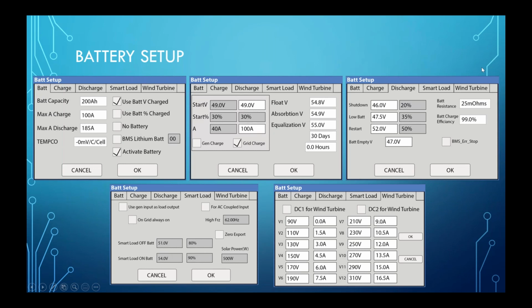And then BMS Error Stop. This is a newer feature that we've added, especially with the comms that we have with most batteries. If there are any times that the BMS shuts off or the communication stops, with this setting you want to have it unchecked, because we don't want the inverter to shut down in those events.